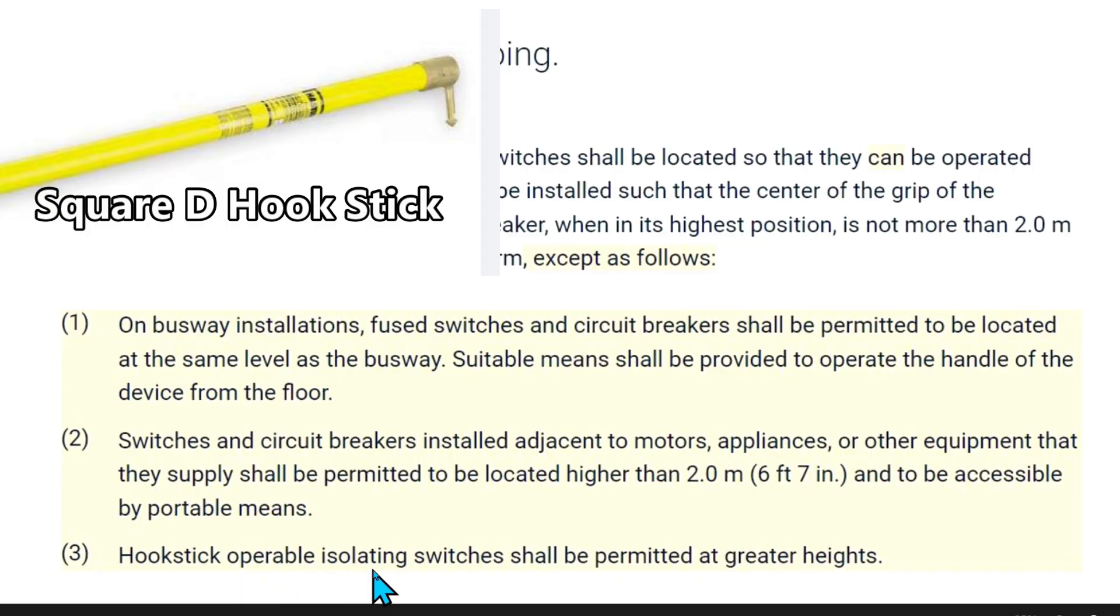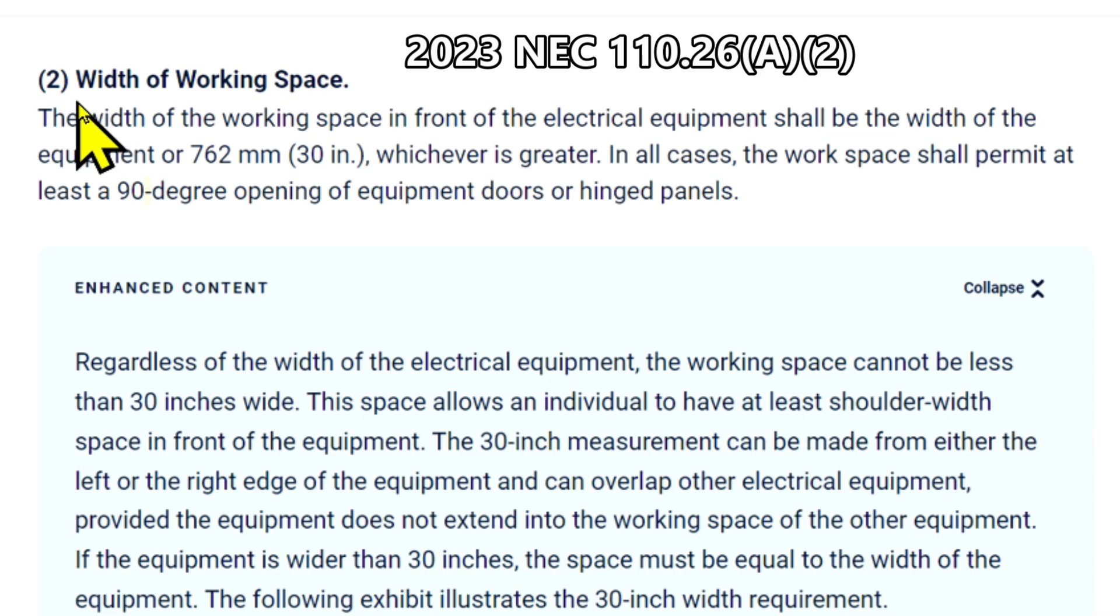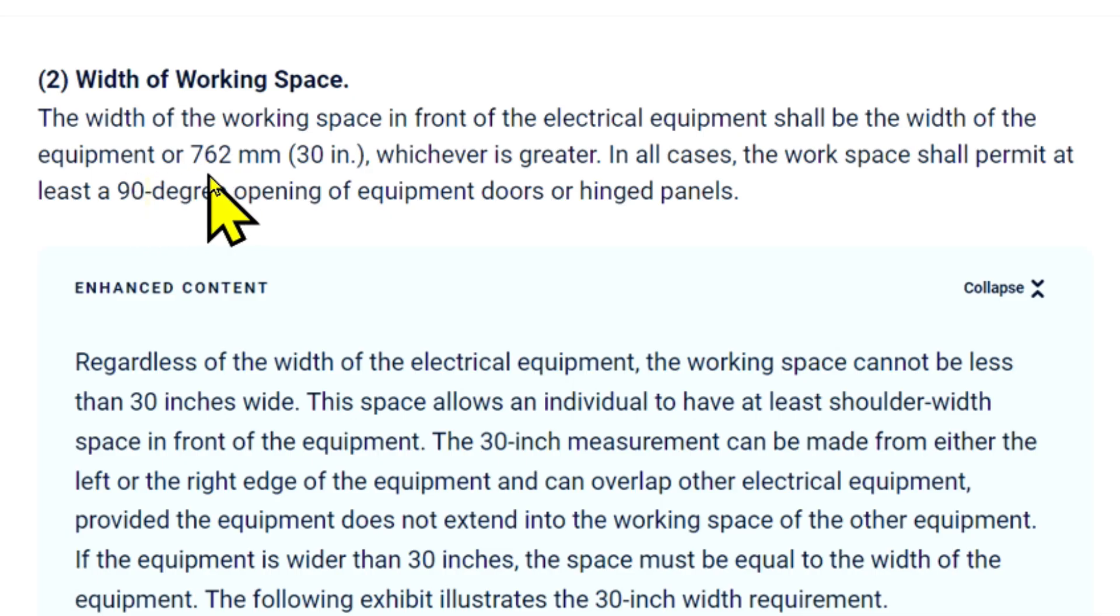Number three, hookstick operable isolating switches shall be permitted at greater heights. 110.26a2, width of working space: the width of the working space in front of the electrical equipment shall be the width of the equipment or 762 millimeters, that's 30 inches, whichever is greater. In all cases the work space shall permit at least a 90 degree opening of equipment doors or hinged panels.